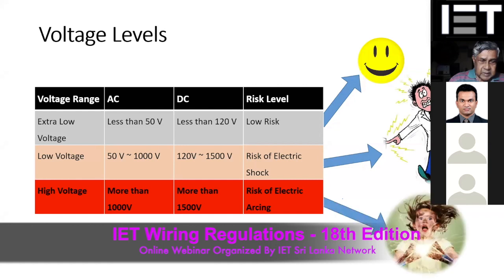The third category is the high voltages. If the voltage is more than 1000 volts, it is considered a high voltage. With that type of voltage, not only electric shock but also electric arcing can occur. Because of that there is a very high risk, and the regulation does not cover that part. High voltage is not covered under the regulation. The regulation basically covers the low voltages and the extra low voltages.